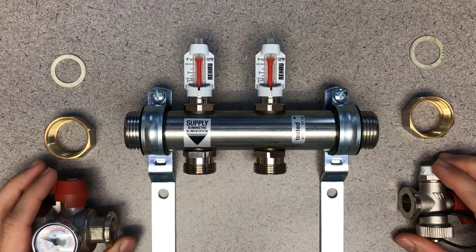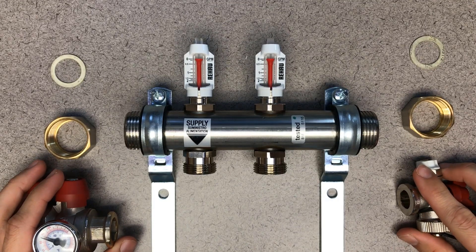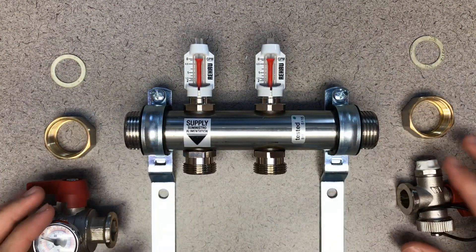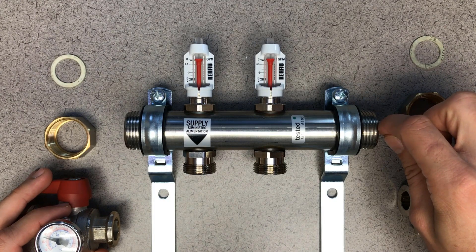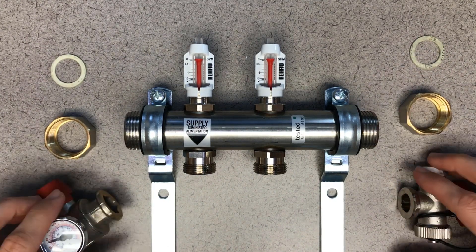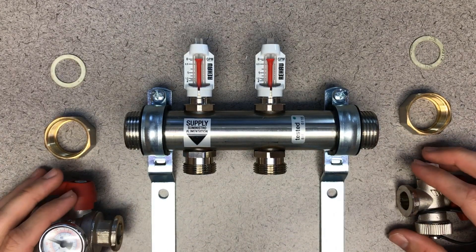In this video, I'll show you how to assemble the isolation ball valves and the air vent drain valves on the REHAU ProBalance 1 inch stainless steel manifold. Either the left or the right for the isolation ball valves and the air vent drain valves is fine — in some cases people will supply the manifold from the right and have the return go out the left, so you can switch those side to side as you please.